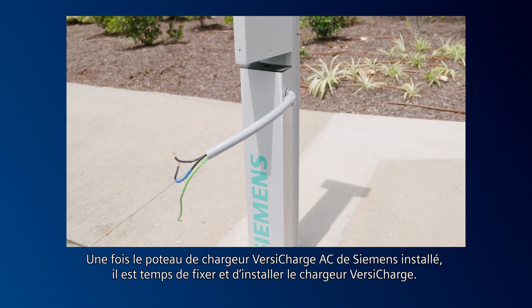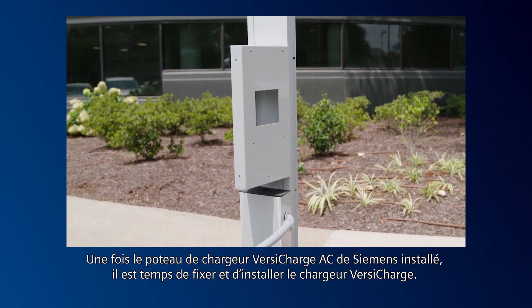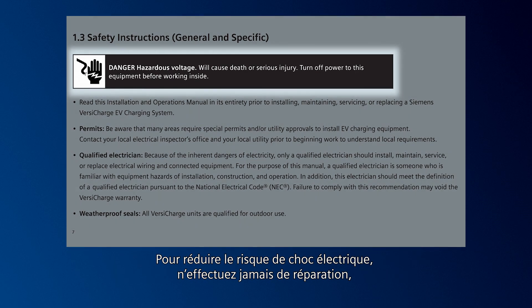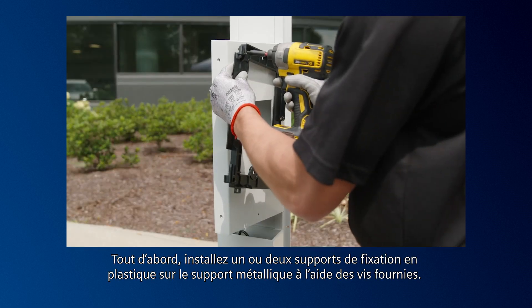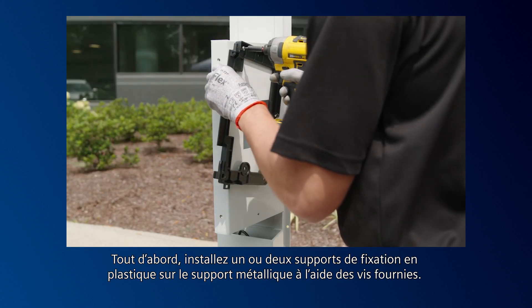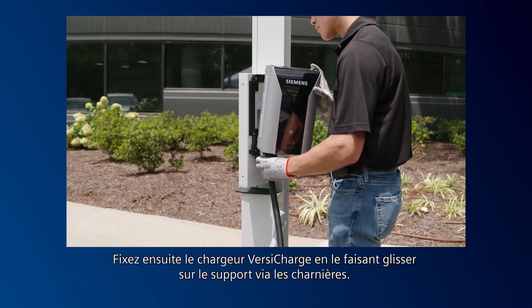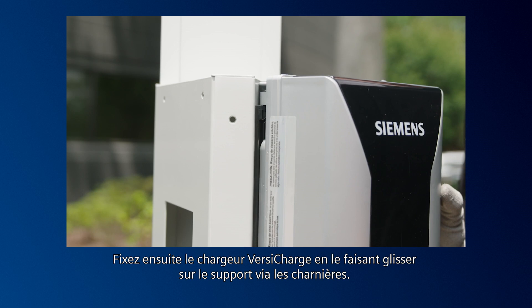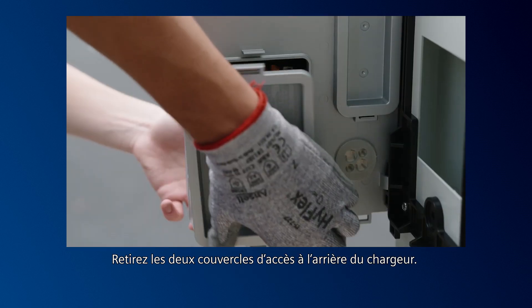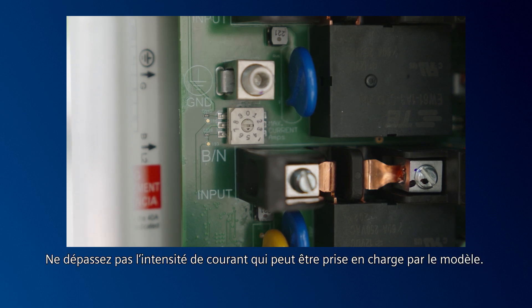Once the Siemens VersiCharge AC charger post has been installed, it's time to mount and install the VersiCharge charger. To reduce the risk of electrical shock, never service, install, or uninstall this VersiCharge while power is flowing to the unit. First, install one or two plastic mounting brackets onto the metal bracket with the included screws. The metal bracket is supplied with the post. Next, hang the charger by sliding the VersiCharge onto the bracket via the hinges, then remove the two access covers on the back of the charger. Find the dial and set the amp switch. Do not exceed the amount of amperage the model can handle.